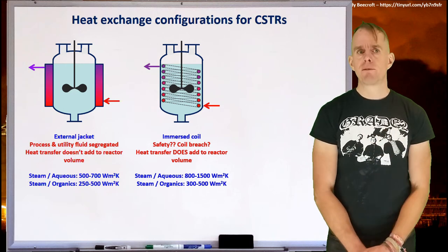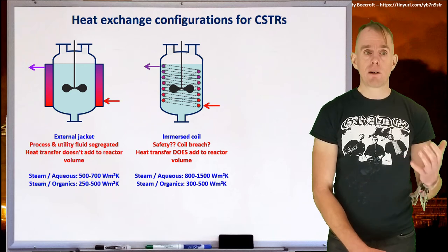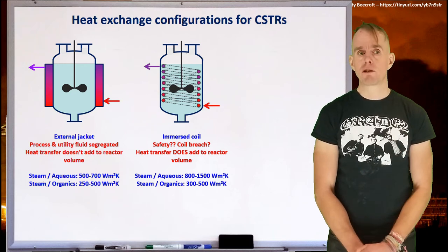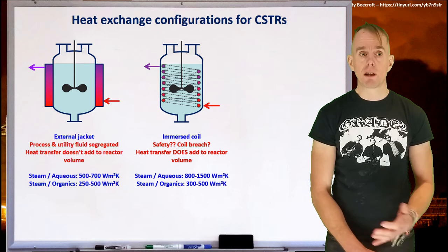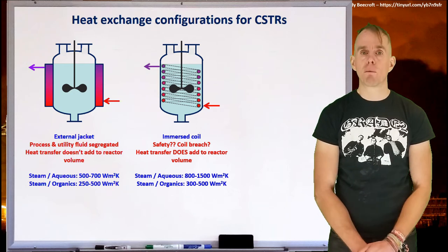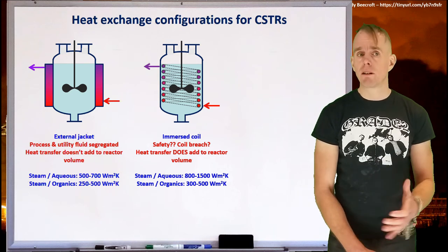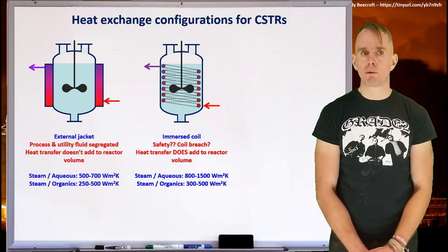The advantage of having a coil inside your reactor, of course, is higher heat transfer. And so if you, again, you're having steam contacting an aqueous mixture, you can get almost double what you might expect from an external heating jacket, 800 to 1500 Watt per square meter Kelvin. And again, steam to organics, you're only still getting about 300 to 500 Watt per square meter Kelvin.